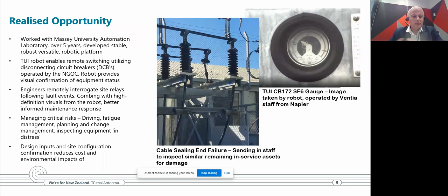The other major thing we've had was a cable termination, a 33 kV cable with a pothead, that failed catastrophically. We were able to put the robot in on a first inspection basis to inspect the failure. More importantly, if the equipment was under distress, traditionally doing that sort of inspection means putting somebody in harm's way. But with the robot, we don't actually need to do that.